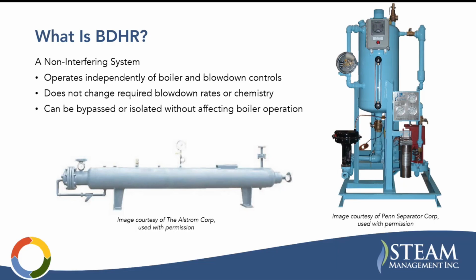It doesn't require a change in blowdown rate or chemistry, although some systems would perform better from a digitally controlled blowdown or more steady flow. But generally speaking, it doesn't change how your boiler is operating. And it could be completely bypassed and isolated, and you could continue to operate as you've always been operating. So it's kind of a passive, not passive, but a non-interfering system that can capture a lot of energy and save a lot of money.